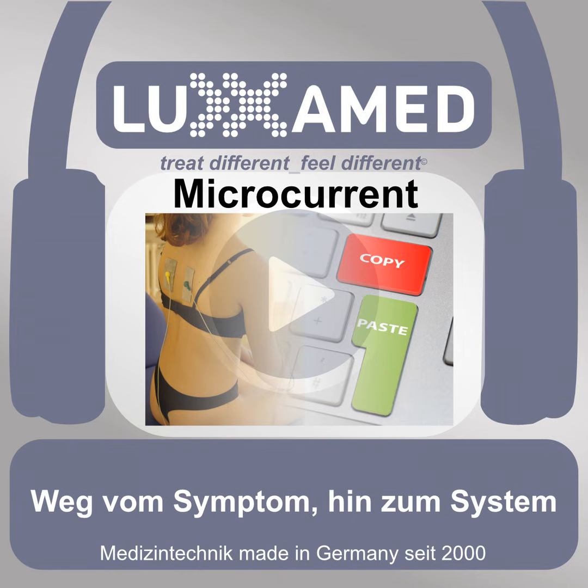If polarity were actually crucial, you have to keep that in mind, it would have to show up in practice in inconsistent results. But logically, that is not the case. The combination of the placement, so red distal, black proximal, is therefore rather a historically grown consistency that is no longer necessary in the actual therapeutic presentation today.